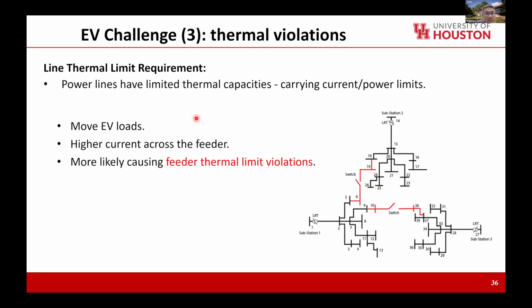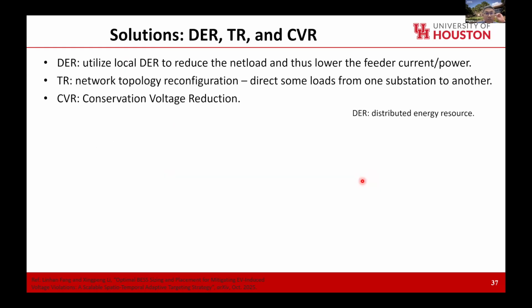A third challenge is the line thermal limit violation. It's again related to the current carried by the feeders. Feeders, power lines, and cables have limited thermal capacity. If they carry too much current, that may exceed their thermal limit. So we could also adopt batteries to address the thermal limit, or we can adopt other types of DER, maybe a diesel generator.